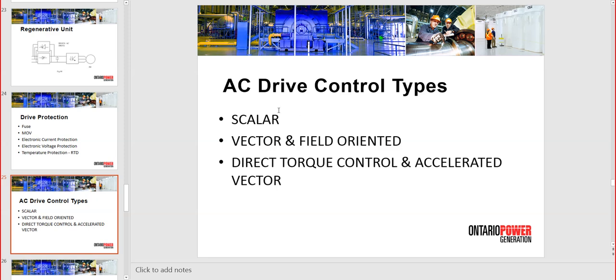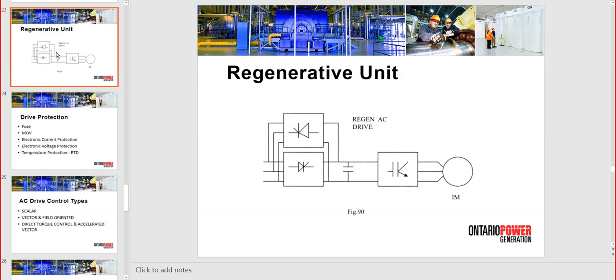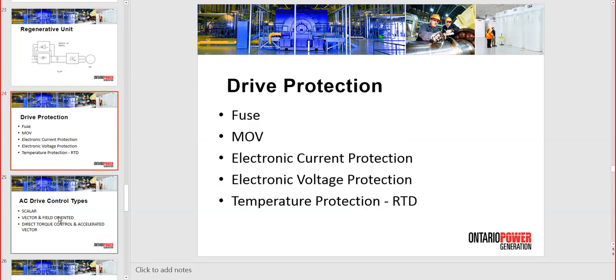So let's review what we did on the power side. We have three types of drives. We have the one on the shelf with diode rectifiers for common application. We have the active front end for regenerative drive that uses IGBTs on the rectifier with force commutation, the new technology, but only available up to 250 kVA. And then we have the active regenerative unit. The regenerative unit is with an extra box that connects to the power whenever you have extra voltage on the DC bus, because the motor became a generator.